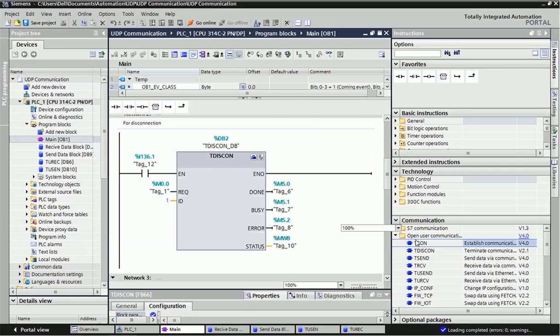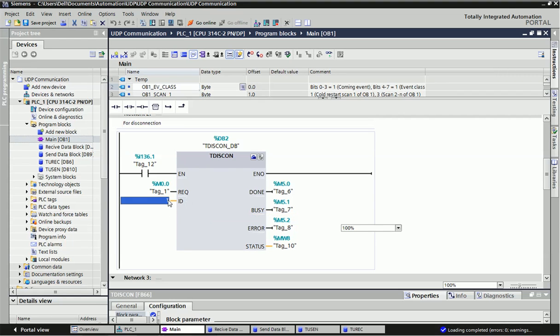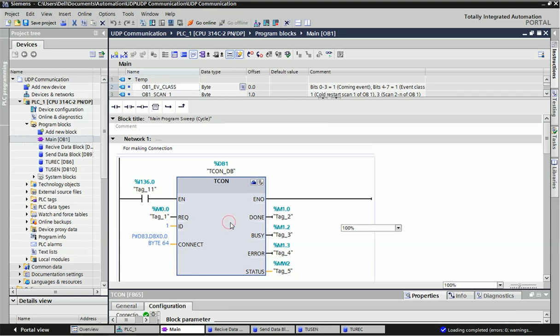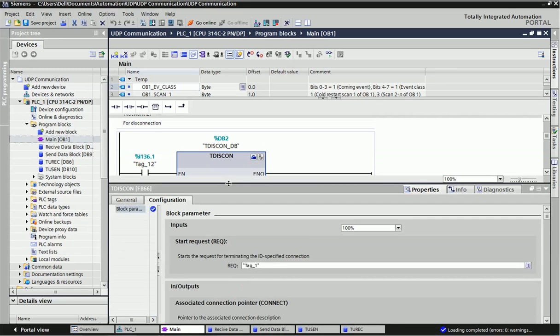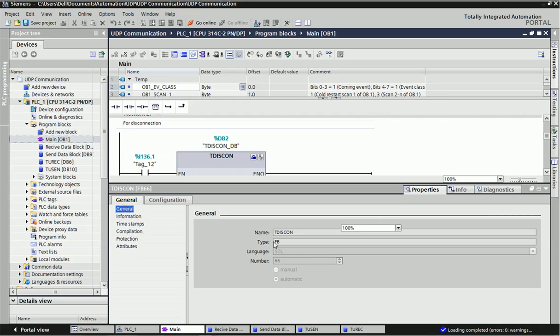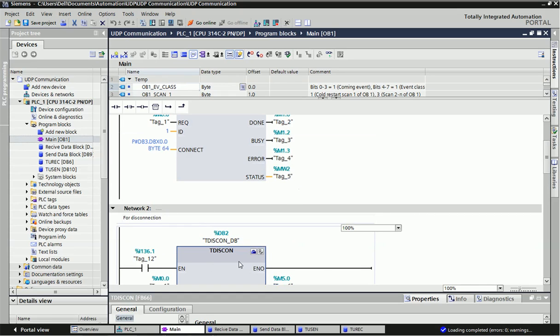From Open User Communication we find the T_DISCON block and drag and drop it. I have used I136.1 to enable this T_DISCON block, with the same M0.0 clock memory for the request pulse. For the ID I will use 1, the same as used in the T_CON block. In the configuration for T_DISCON there is no further parameterization required — we only assign the done bit, busy, error, and status memory word. These are the two blocks for making and terminating the connection for UDP.